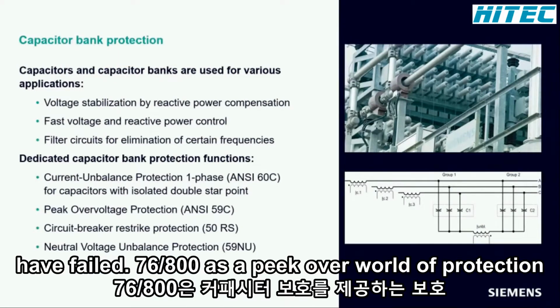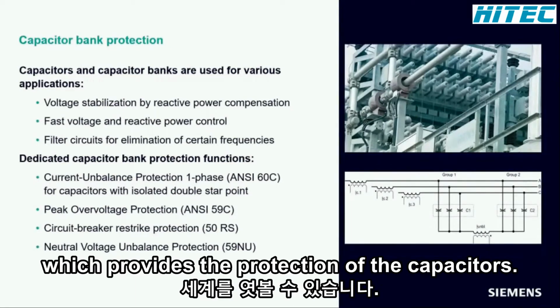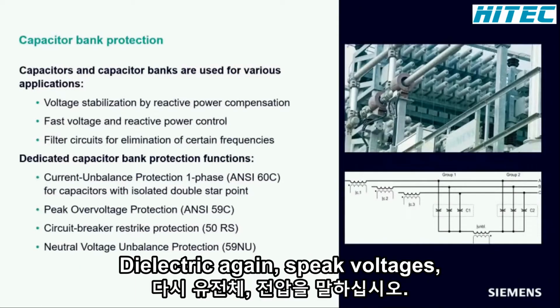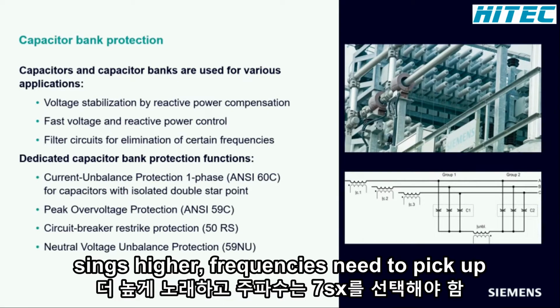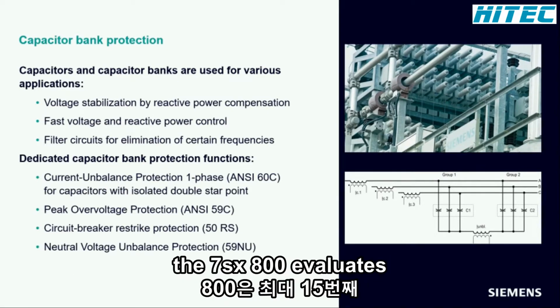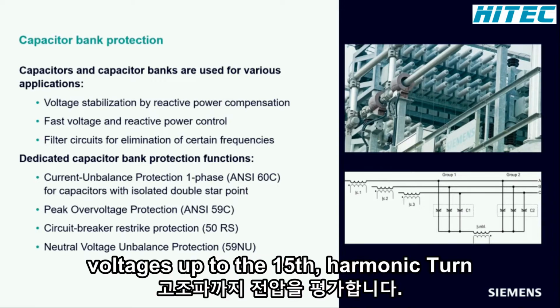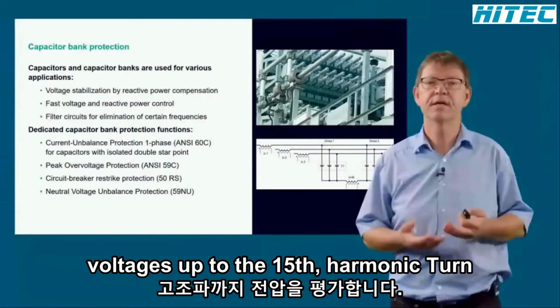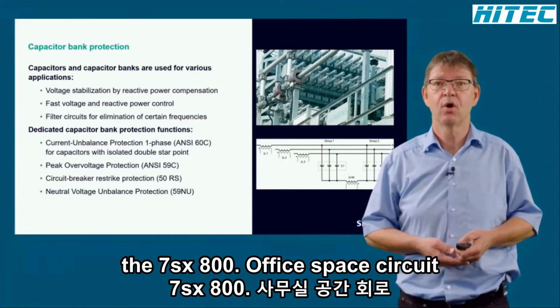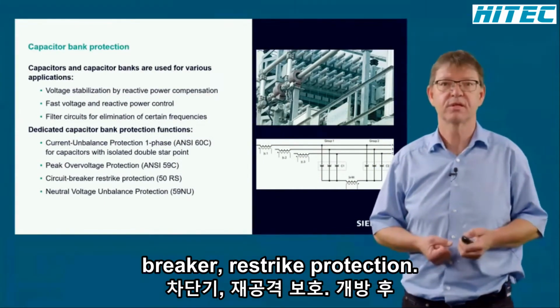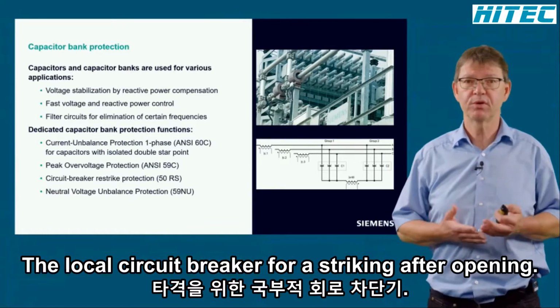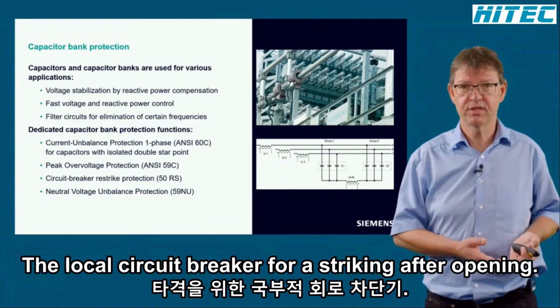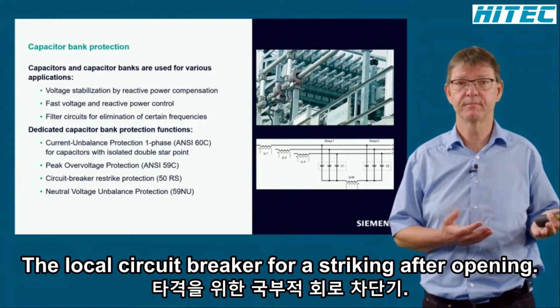7SX800 has a peak overvoltage protection, which provides the protection of the capacitor's dielectric against peak voltages. Since higher frequencies lead to bigger currents, the 7SX800 evaluates voltages up to the 50th harmonic. Then the 7SX800 offers a circuit breaker restrike protection. This function monitors the local circuit breaker for restriking after opening.